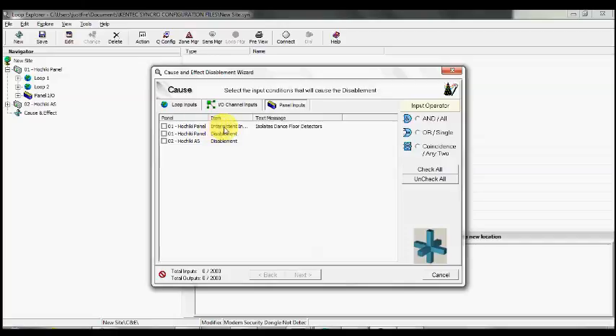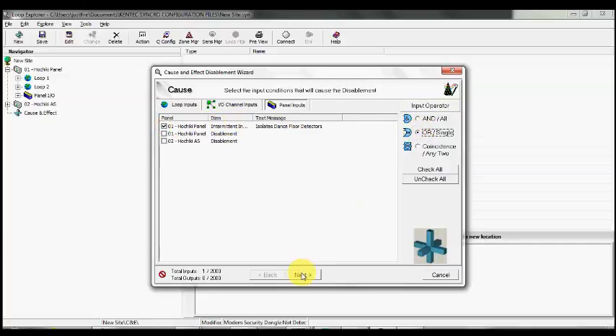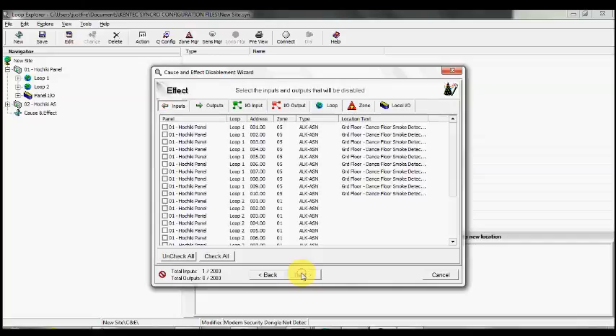I select the panel inputs. There's the input that we reassigned to be a disablement type input. I'm going to tick the box. It's going to be an OR event—just this input operating will cause the event. Next, we need to select the inputs and outputs that will be disabled.